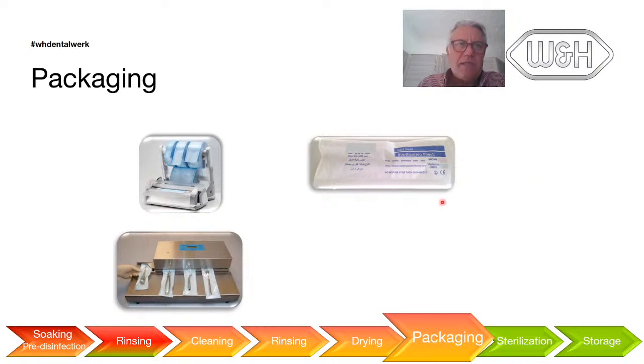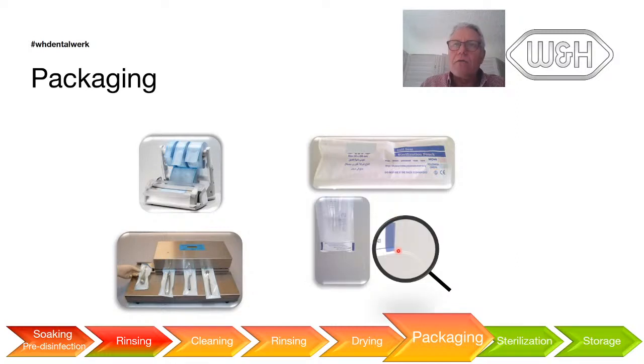These are welding devices, nothing to explain here. If you have single-use pouches, it's fine to me, but you will have to do a test before you reuse them. Please fill them with water to one third. Then you seal your pouch and you put it upside down. If you see water pouring out, this means that it's not sealed properly, so it's not going to be maintained. The instruments are not going to be maintained sterile inside the pouch. Two reasons: either the pouch is not of good quality, or you have not folded it properly. Inside here you have a strip, a mark that shows you where to fold the pouches.